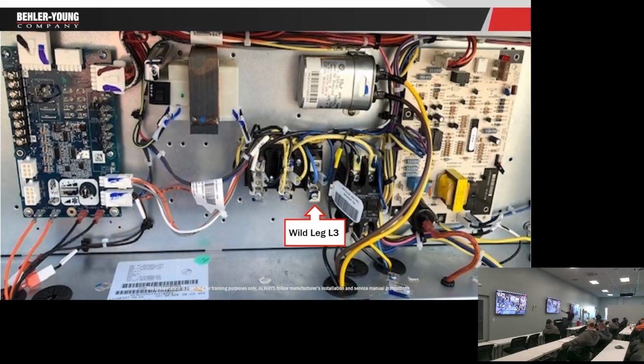So again, wild leg on blue, which is L3. This is really kind of cool once you know this. This yellow wire going to this capacitor, guess what? That's L2. This black wire right here, that's L1. So anywhere in the unit where you see a yellow wire, it's L2. Any black wire is L1, and any blue wire is L3.